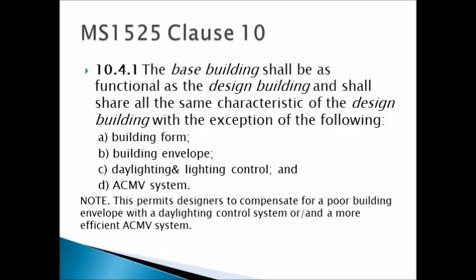So when you're designing, the base building shall be as functional as the design building. The base building, remember, the shoebox building, that means it's a plain rectangular building, and shall share all the same characteristics of the design building with the exception of the following. Of course, the building form will change.